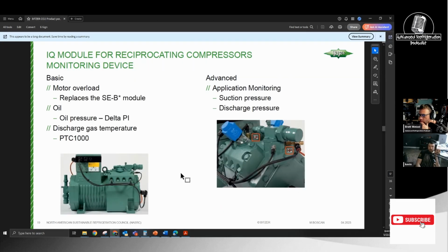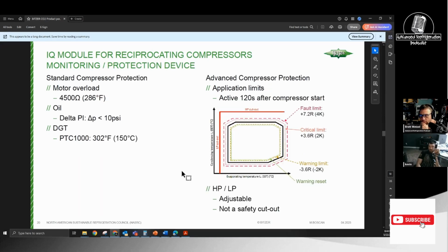When I sized these, it matters what operating envelope you're in, because in some cases you may not be able to unload all three heads, since it may need the cooling. In some low temp situations you may not be able to unload all three heads. You've got to look at the Bitzer software we use to check compressor efficiencies, and make sure you can set it up for VARISTEP and stay within an operating envelope.